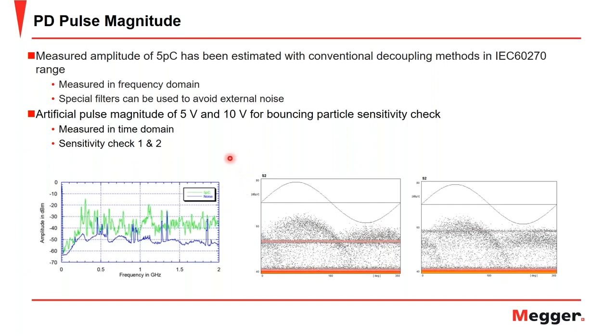And the next step, while still at the manufacturer, is to inject a voltage signal between 5 and 50 volts into sensors nearby to find a signal strength that best fits the peak value of that 5 picocoulomb pattern. So for instance, you have an artificial pulse magnitude of 5 volts injected, and you can see where it lines up on the PRPD pattern, not quite at the peak. So if that's increased to 10 volts, you can now see that the injected signal aligns well with the peak of the 5 picocoulomb pattern seen here.